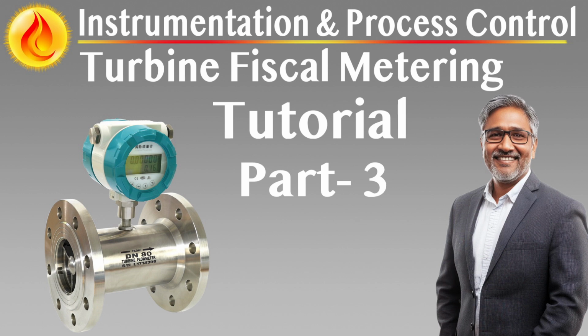Flow conditioning and meter run integration. Turbine meters must be installed with appropriate upstream and downstream pipe lengths and flow conditioning elements. Minimum straight pipe lengths of 10 internal diameters upstream and 5 diameters downstream must be maintained. Flow straighteners or meter tubes must be included where necessary to eliminate swirl and profile distortion, ensuring the rotor is exposed to a symmetrical velocity distribution. The entire meter run must remain liquid-filled under all flow conditions, including static or zero flow states, to prevent gas pockets or cavitation that would compromise pulse accuracy and meter longevity.